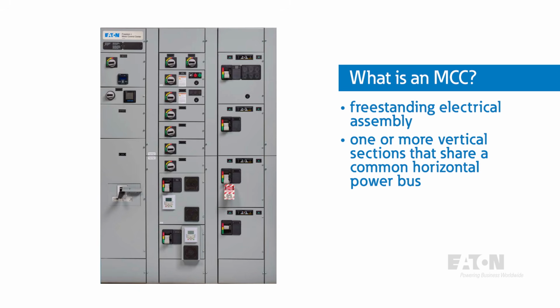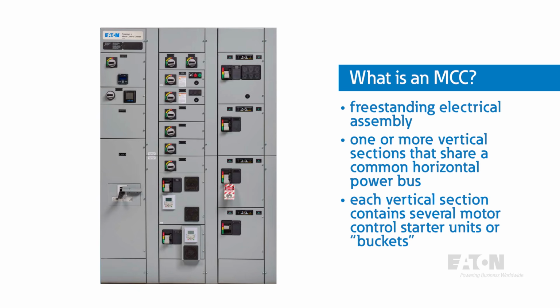An MCC is a freestanding electrical assembly comprised of one or more vertical sections that share a common horizontal power bus. Each vertical enclosed section typically contains several motor control starter units or buckets, with each getting power from a vertical bus that connects to the horizontal bus.